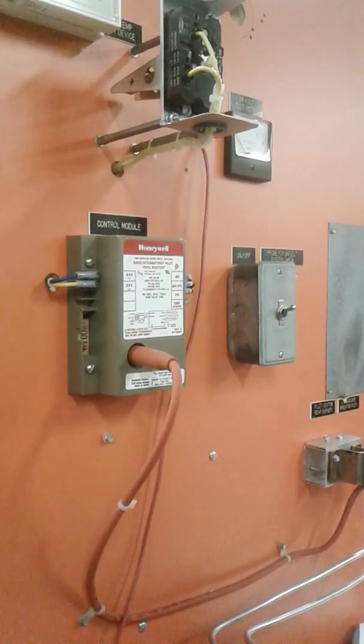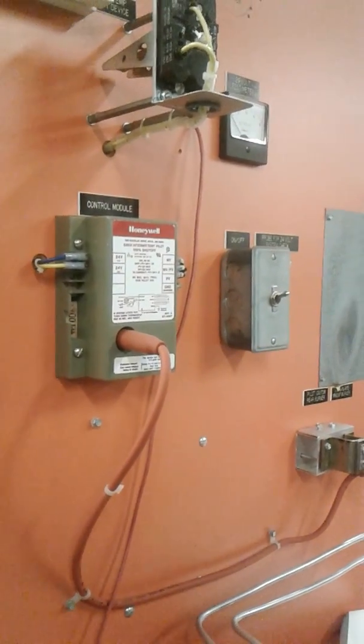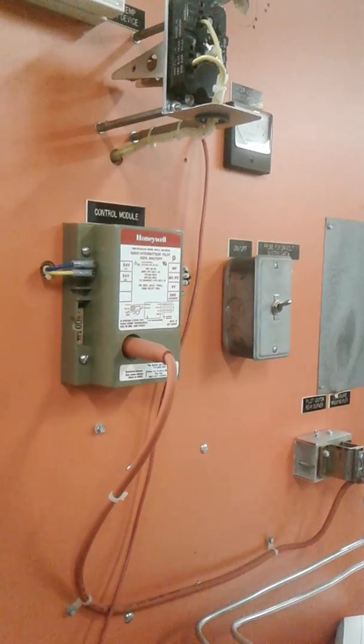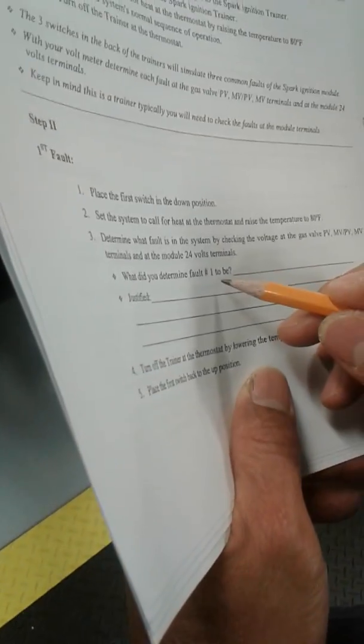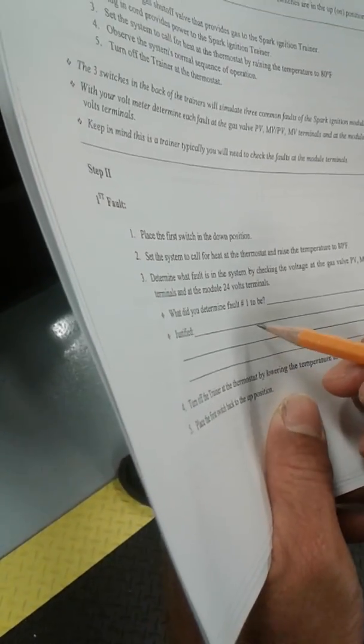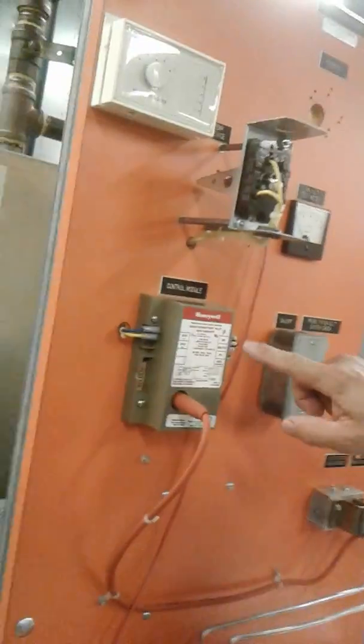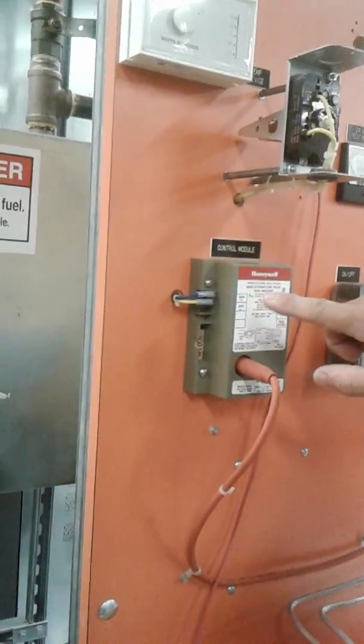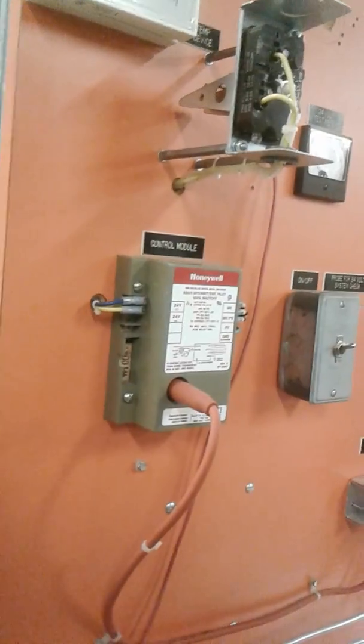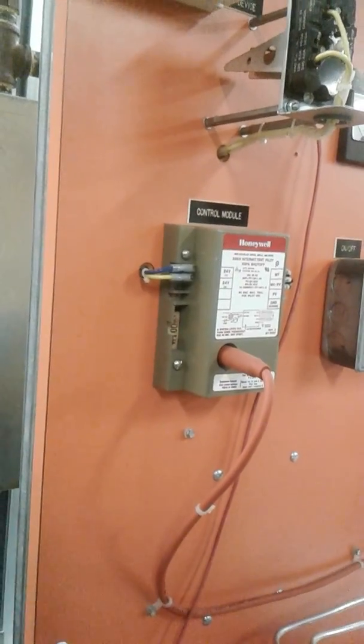So that's fault 1. Okay? So, it says here, what did you determine fault number 1 to be? Like he said, bad transformer. Bad transformer. Why is it a bad transformer? Justified? Why is it a bad transformer? Because we have no 24 volts being supplied to our control module. Okay?